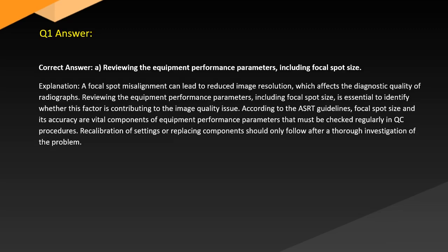Answer. Correct answer A. Reviewing the equipment performance parameters, including focal spot size. Explanation. A focal spot misalignment can lead to reduced image resolution, which affects the diagnostic quality of radiographs.